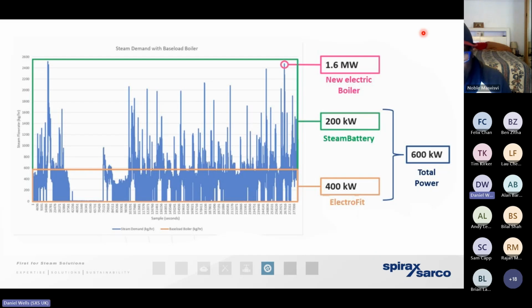Now, as I mentioned at the start of the presentation, there's no magic bullet. There's no single steam generation solution that is going to be a good fit for all of our clients. But if a client wanted to choose a brand new electric boiler, that would need to be sized to accommodate those spikes, that maximum instantaneous peak demand. But if they accommodated a steam battery, then a steam battery would be able to provide that huge surge of instantaneous thermal demand very, very easily.